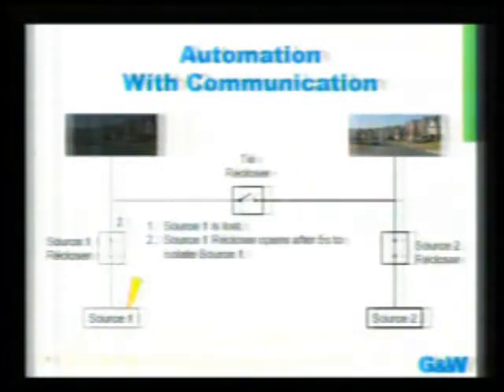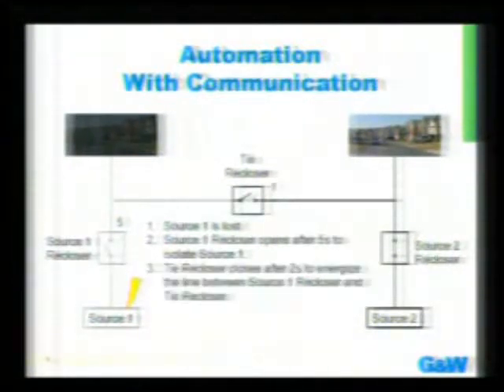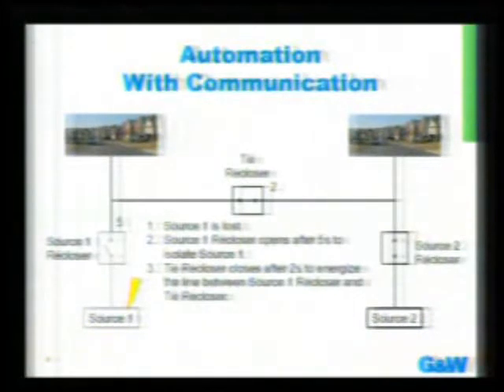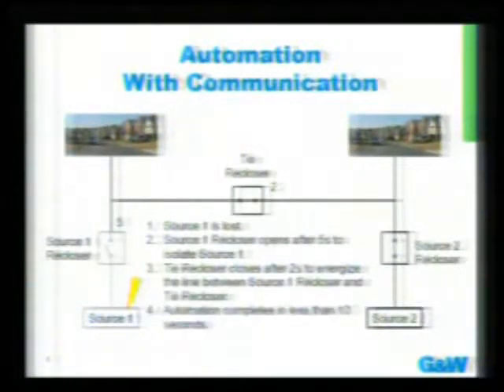Source one is lost. The recloser counts to 5 seconds and then opens. Now the tie is counting 2 more seconds, and it closes. We've been able to reroute power from an alternate source to feed both of our loads automatically. Using communication—while it takes a bit more technology to achieve this—automation and rerouting of power can be done in fewer than 10 seconds, rather than on the time scale of one minute.